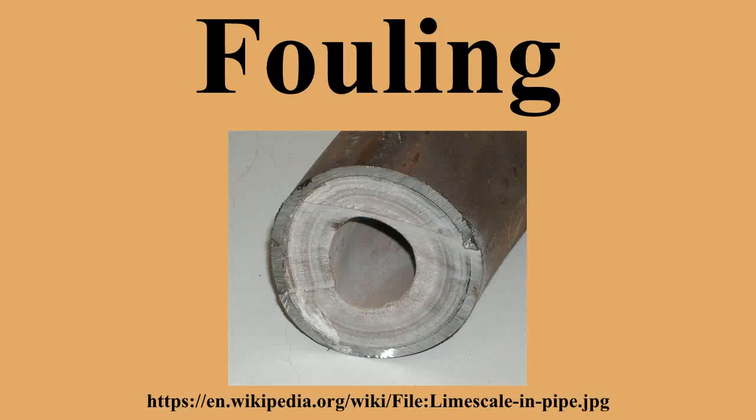Accelerating fouling. Under this scenario, the fouling rate increases with time. The rate of deposit buildup accelerates with time. Mechanistically, this scenario can develop when fouling increases the surface roughness, or when the deposit surface exhibits higher chemical propensity to fouling than the pure underlying metal.